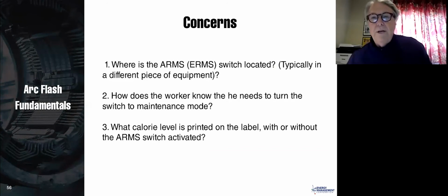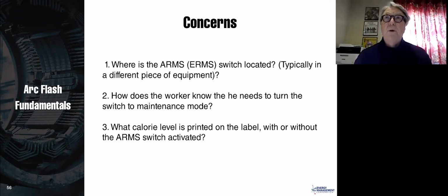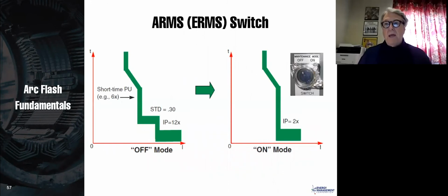How does the worker know he needs to turn that switch to maintenance mode? And what calorie do you print on the label of the motor control center? Do you print there the calorie in maintenance mode, or do you print there the calories in normal mode? And we tend to say that we want to print the calories in maintenance mode because you shouldn't be working on it if it isn't in maintenance mode. But then we put a big warning right on the arc flash sticker that says you must turn the ARMS switch to the maintenance mode, and here's where that breaker is. So some concerns, and that shows what happens when you go off and on.